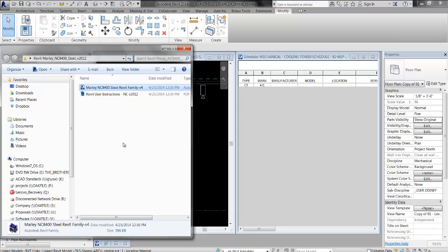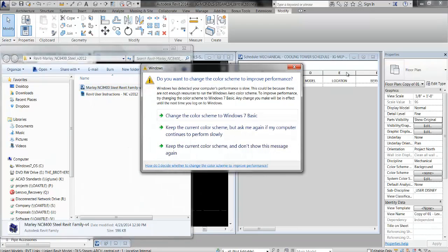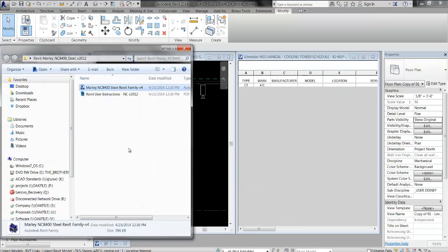For example, Greenheck often has one Revit family for a whole broad genre of fans, and then they also release a text file along with it. So when you load it in, it pops up with a little window that says, which models do you want? Do you want the SBS24 blah blah blah? And then you pick all the ones that you want and then load them in. However, if you drag and drop, Revit's not going to notice that text file, and it'll just do something random and screw you over. So the best practice with vendor families is to load in the family from your project.